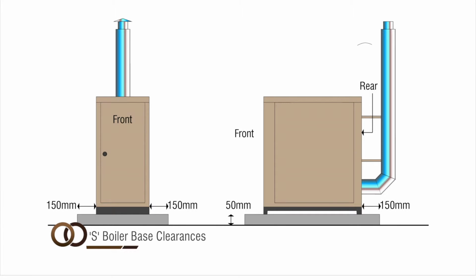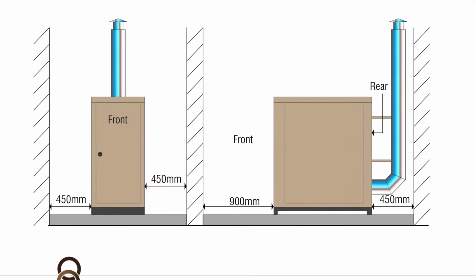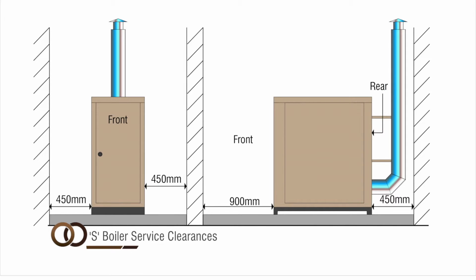For the S model boilers, the base needs to be 50 mm high and should project a minimum of 150 mm beyond all sides of the boiler. Service clearances must be at least 900 mm to the front and 450 mm to the rear and both sides of the S model boilers.